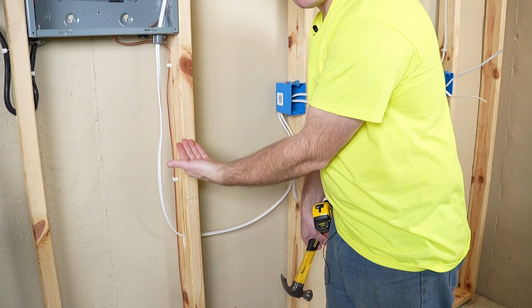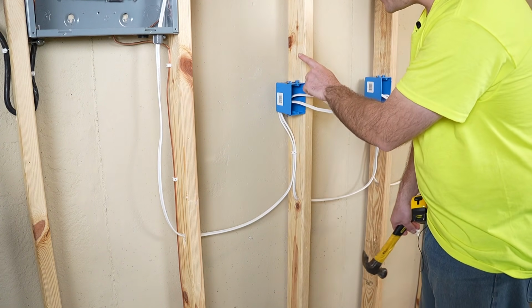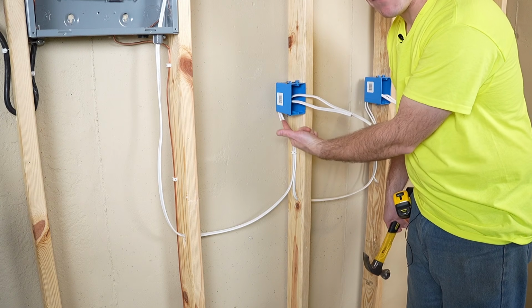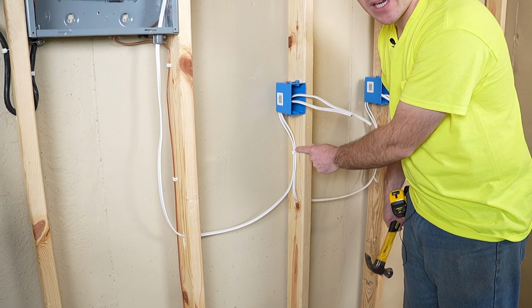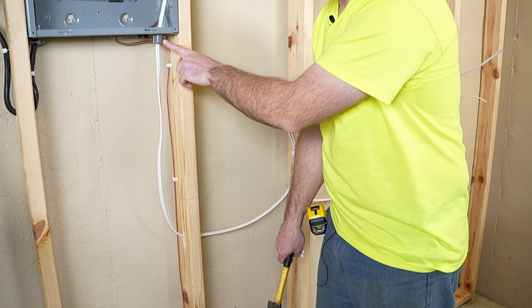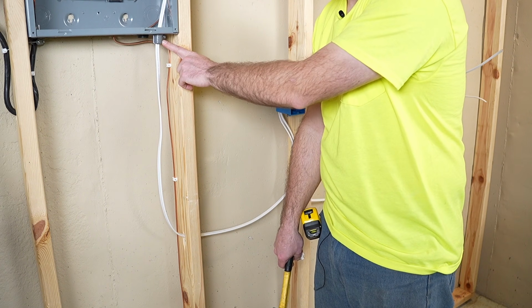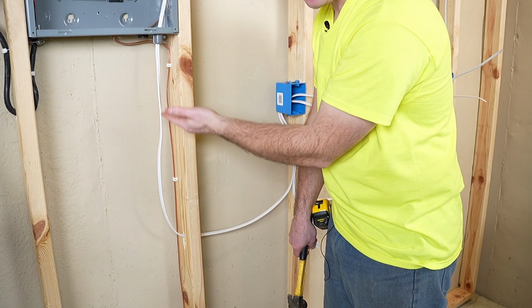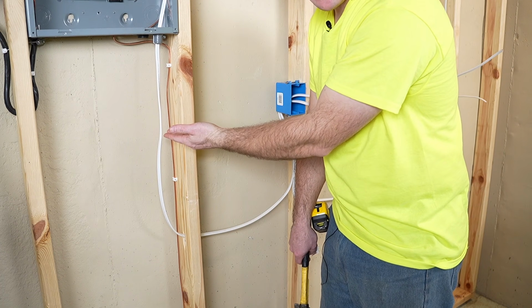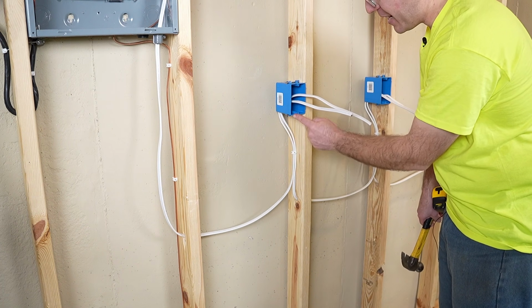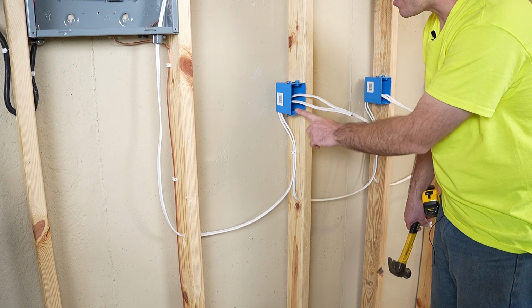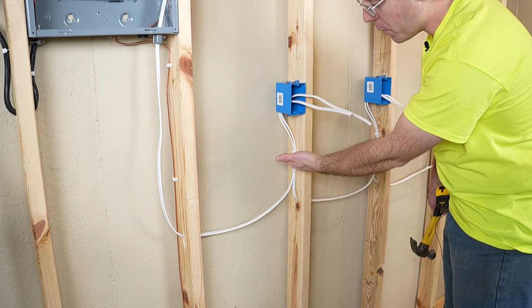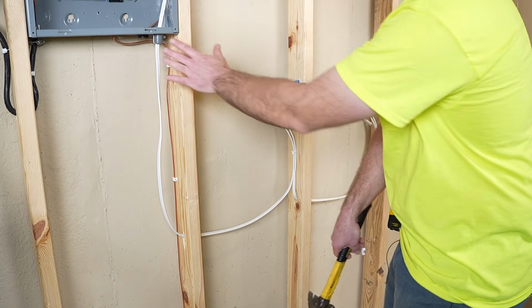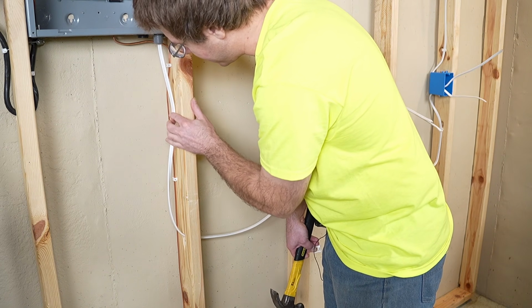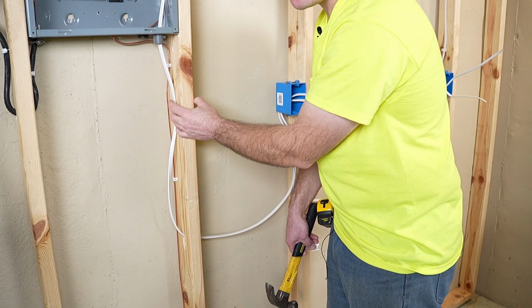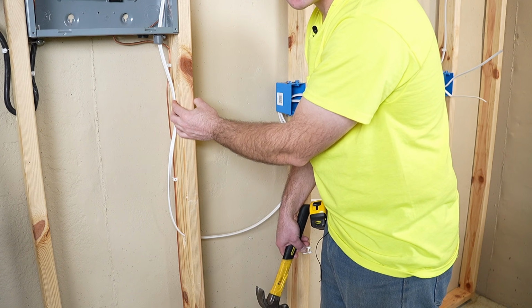And finally, we have the strap coming out of the panel. Now, these non-metallic boxes had no clamping mechanism in them, so we had to strap within 8 inches. This connector that we installed in the panel, however, is considered a clamping mechanism. So we need to strap within 12 inches of the panel. These were an exception because they don't have a clamp mechanism in them. If these had a clamp mechanism, we could have strapped within 12 inches. So we just need to strap within 12 inches of the panel. Again, we also want to make sure the cable is within the center of the stud.